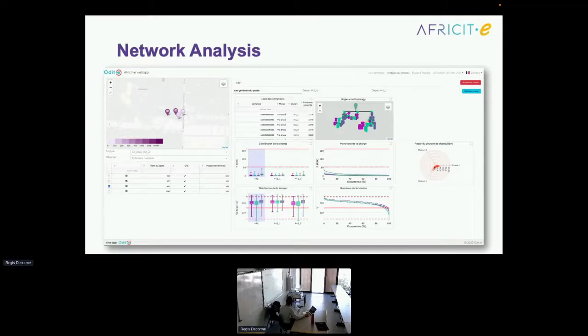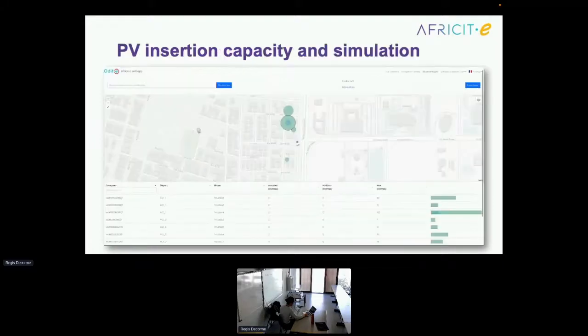This is mainly because of imbalance in the network. And then we provide them as well with a PV insertion capacity and simulation tool, based on the previous model. This software gives the information about how much PV panels can be implemented at one given smart meter without creating any additional voltage issues on the network, and allows us to simulate what would be the impact of one new installation on all the remaining capacities.